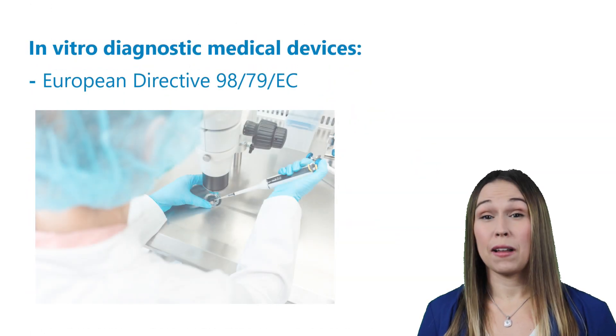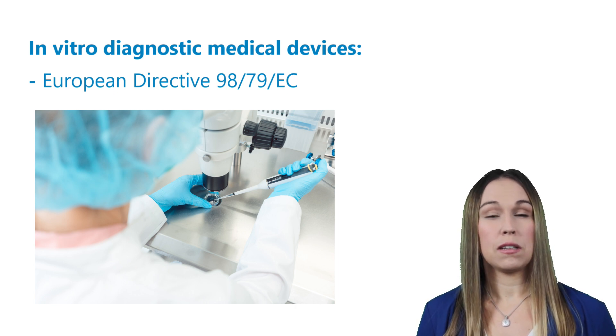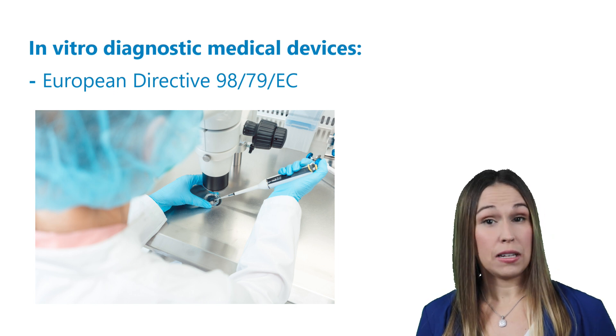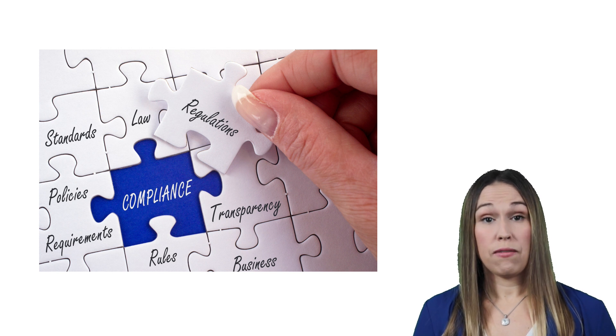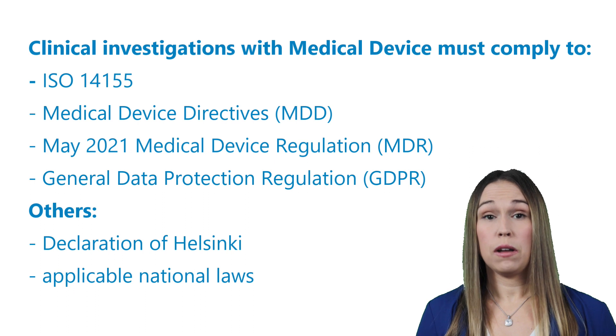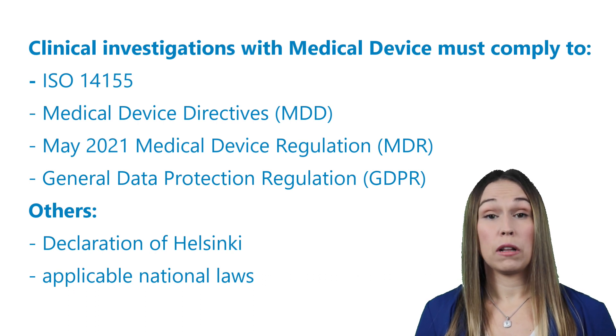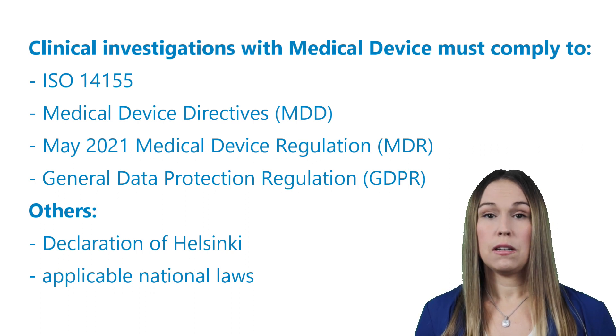This document does not apply to in vitro diagnostic medical devices, which can generally be grouped as devices needed to process and/or examine specimens taken from the human body. These IVDs are subject to the European Directive 98/79/EC IVDD. In addition to ISO 14155, clinical investigations in Europe must comply with the Medical Device Directives, or MDD, and from the 26th of May 2021, with the European Medical Device Regulation, or MDR. Clinical investigations must further comply with relevant provisions of the EU General Data Protection Regulations, or GDPR, 2016/679.